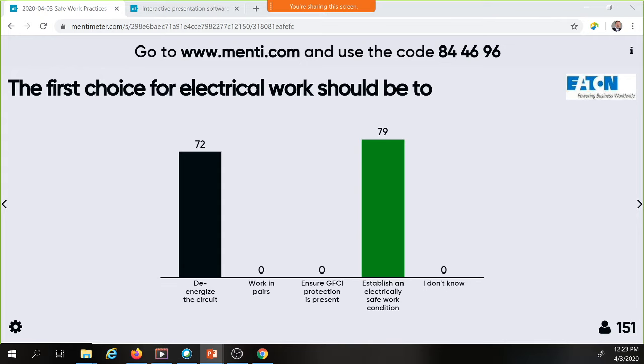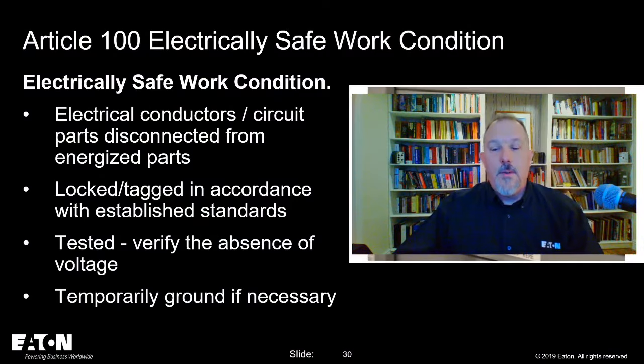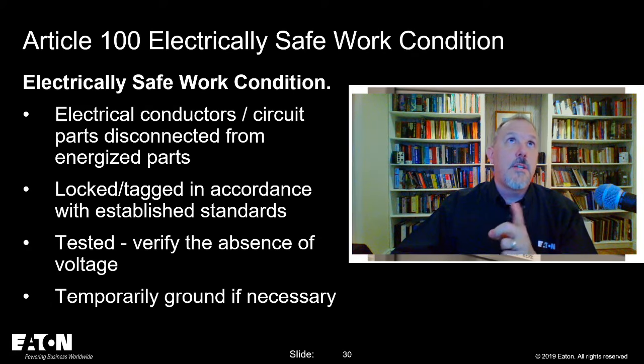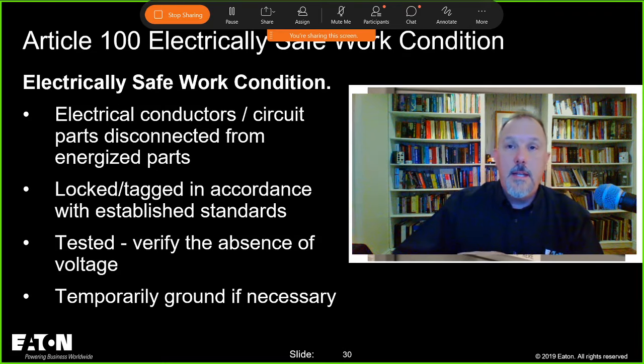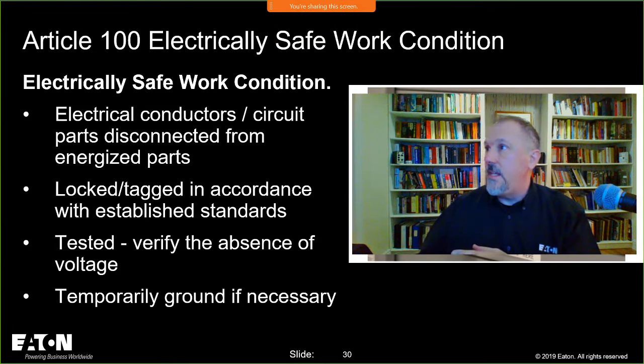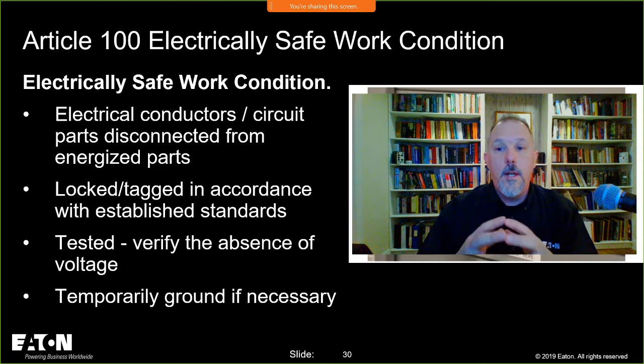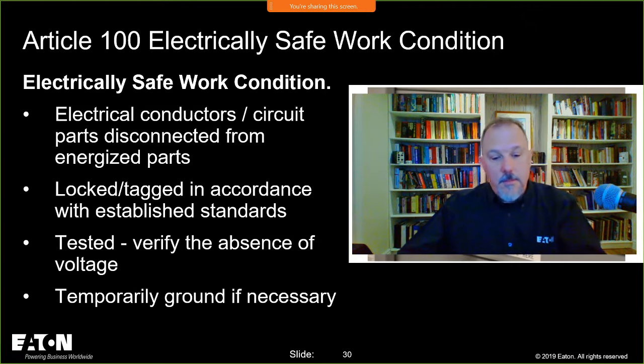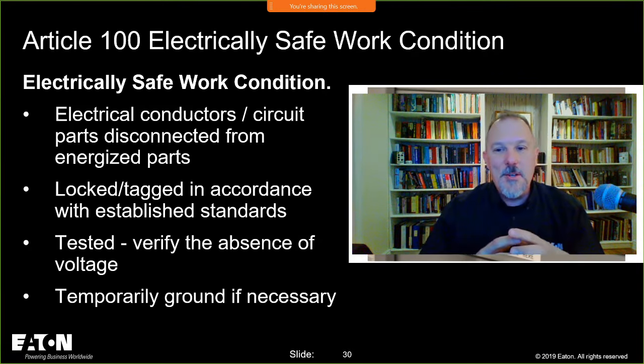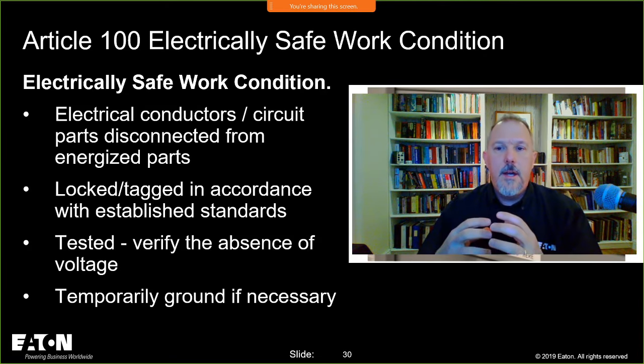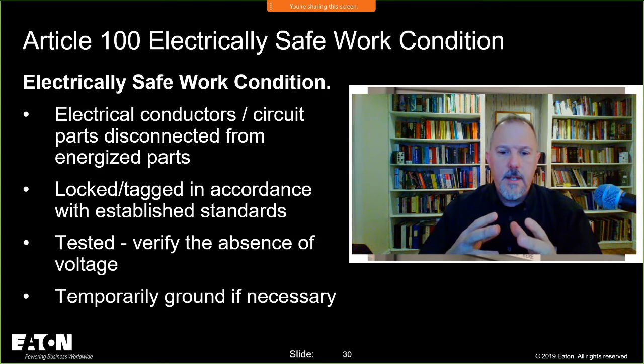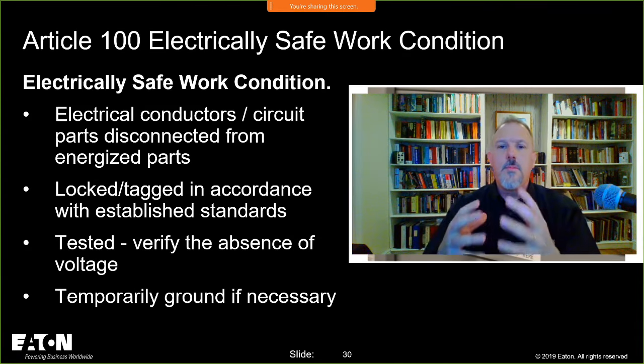I know that it's very important that we follow the right procedures, and we follow 70E, the practice of 70E, and 70E tells us that we have to establish an electrically safe working condition. In fact, there is an entire section in 70E that speaks to that. If we look at Article 100 of 70E, there are some similarities between 70E and the NEC.